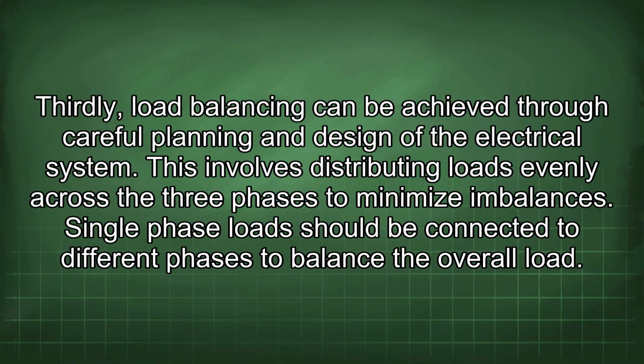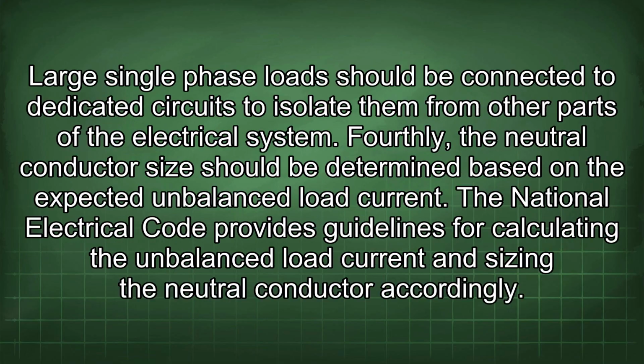Thirdly, load balancing can be achieved through careful planning and design of the electrical system. This involves distributing loads evenly across the three phases to minimize imbalances. Single-phase loads should be connected to different phases to balance the overall load. Large single-phase loads should be connected to dedicated circuits to isolate them from other parts of the electrical system.